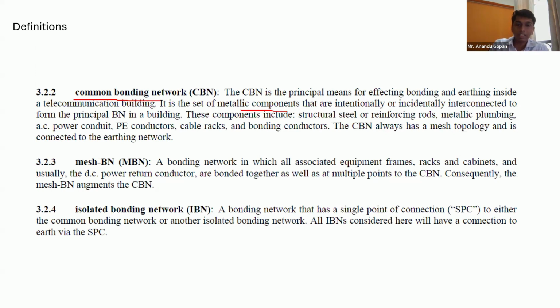Every metallic component must be bonded. These components can include structural steel or reinforcing rods. You will have your metallic plumbing. If you have plastic plumbing, no issues. If you have your AC power conduit, obviously you will have metallic conduits. You are supposed to interconnect them. You will have your PE conductor, which you are supposed to interconnect. You will have your cable racks, bonding conductors, telecommunication bonding conductors, which you are supposed to interconnect. Yes, this will form a common bonding network. This is generally called the common bonding network.